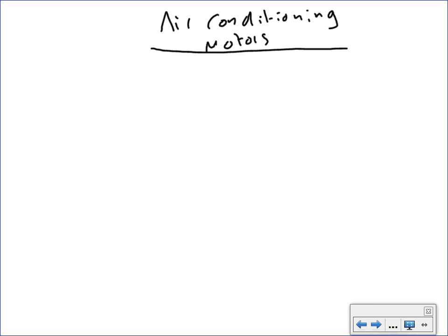Okay. Now HVAC or AC, air conditioning motors. Motors, which is basically air conditioning motors, guys, are compressors. They're a special type of motors designed to work with compressors. They use this code because they are special, because they work with compressors and refrigeration, and this will cover refrigeration equipment, anything that has a chilling effect, as in compressors. You compress the refrigerant and circulate it to get cold, creating cold. Does that make sense? Refrigeration equipment and cooling equipment. That's what it covers. This article is Article 440, right after Article 430, because they're cousins.